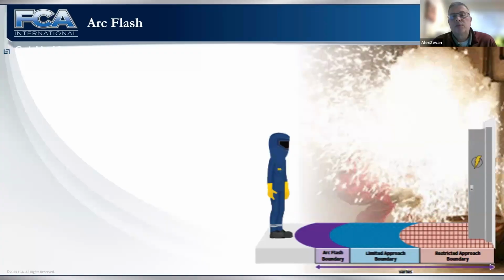This is something that is watched closely to make sure people in the field learn to wear the proper PPE, stand away, and prepare themselves. The blast was intense from contact and grounding out that area. Here are examples of three different critical distances: the arc flash boundary, the limited approach boundary, and the restricted boundary. These are determined based on engineering, with a label placed on the electrical source so individuals working in the area know the distance and what PPE to wear.